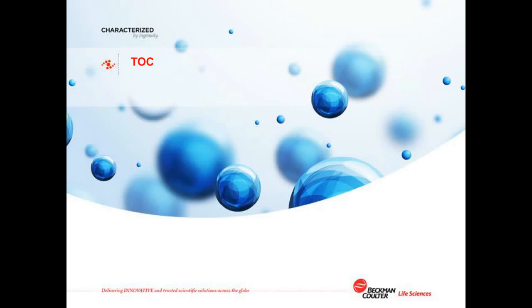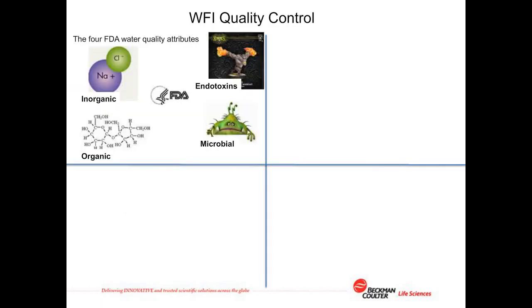So let's take a look at total organic carbon, just what it is and how it's measured. The FDA mandates four critical water quality attributes: monitoring for inorganic contaminants using conductivity, monitoring for TOC, monitoring for endotoxins, and microbial colony forming units.